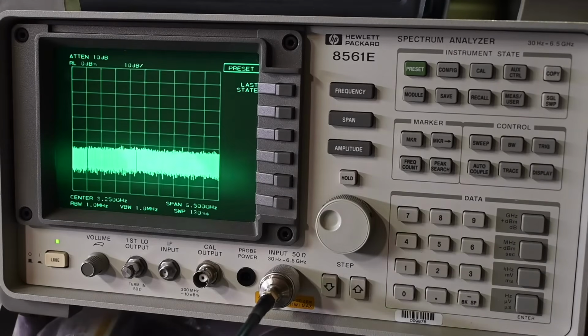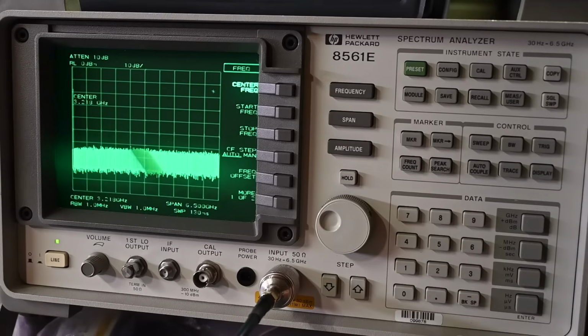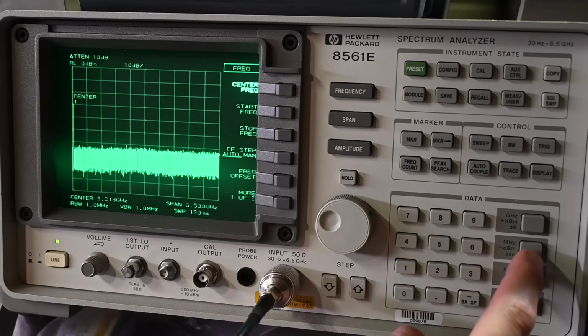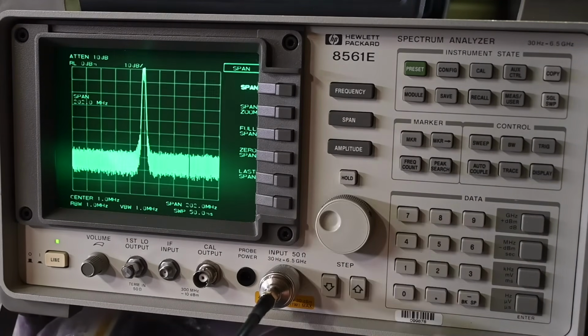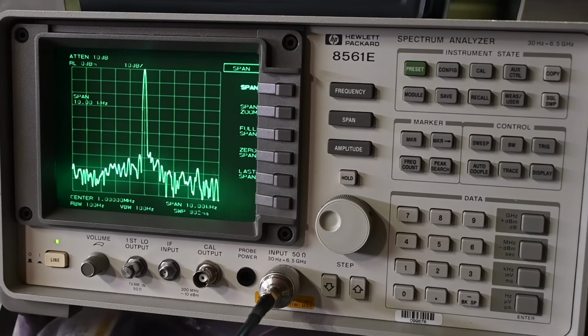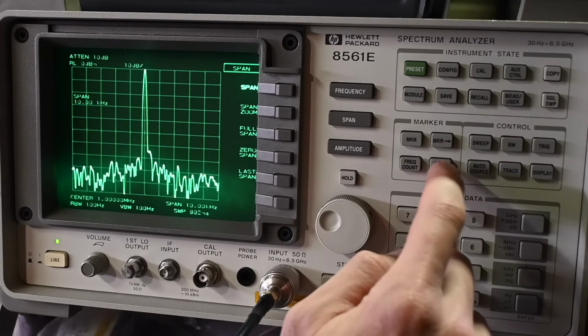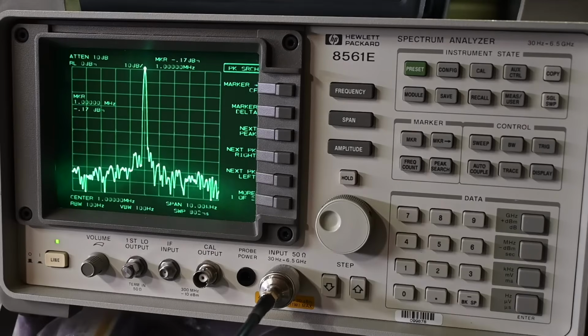There it goes. So over here, I need to go to frequency, and center frequency should be 1 megahertz. And the span, let's make the span 10 kilohertz. All right, and do peak search. So that looks very good. You can see on the marker right now, it's at minus 0.17 dBm, and there's about 6 feet of cable between the signal generator and the spectrum analyzer, so there'll be a little bit of loss in that cable, so no problems there. And the frequency looks to be quite accurate, no problems, sitting right at 1 megahertz.